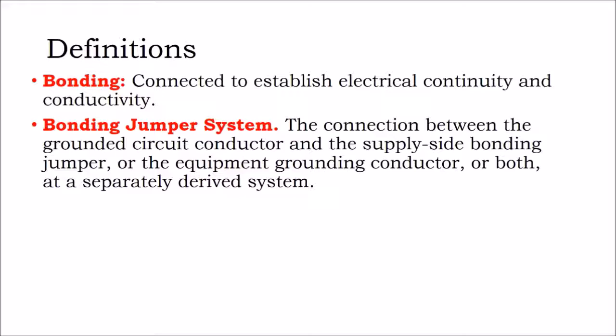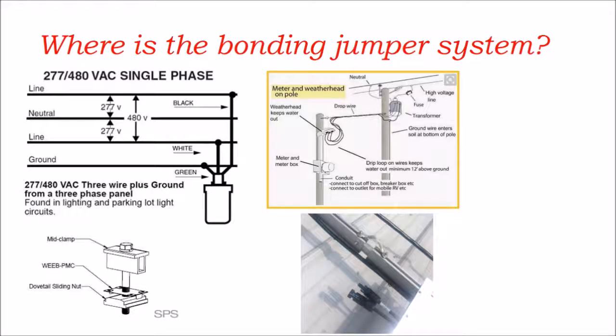So, whether you say the metal is bonded to the equipment ground conductor or all metal parts are grounded, I guess saying that the metal is bonded to the equipment ground conductor is more specific than just saying all the equipment is grounded. All of the metal parts on your systems must be bonded together.